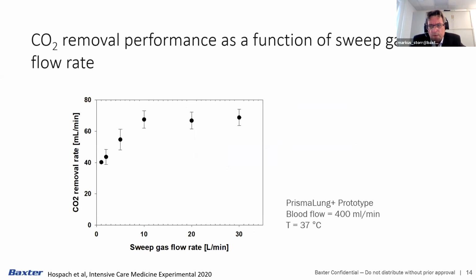So here we see the nonlinear relationship between sweep gas flow, and we used air as sweep gas, and CO2 removal rate. The test was done with a PRISMALUNG Plus prototype device, and we can see a marked increase in CO2 clearance from a gas flow rate of 0 to 5 liter per minute, reaching a plateau after 10 liter per minute for a device blood flow of 400 mL per minute. Since we saw this plateauing effect, we set the sweep gas flow at 10 liter per minute for the subsequent investigations.